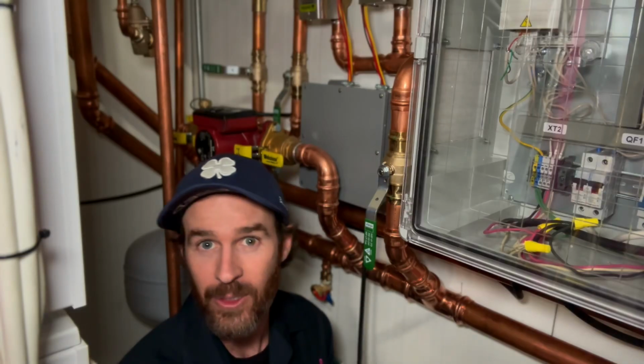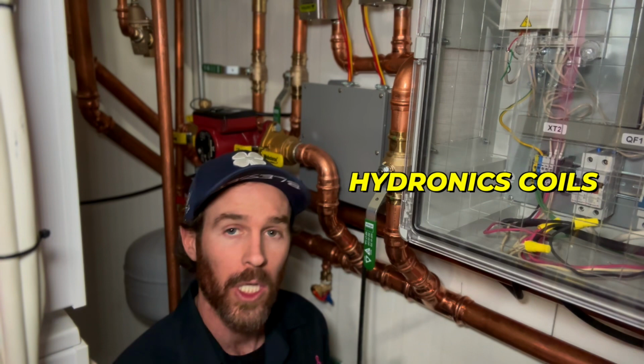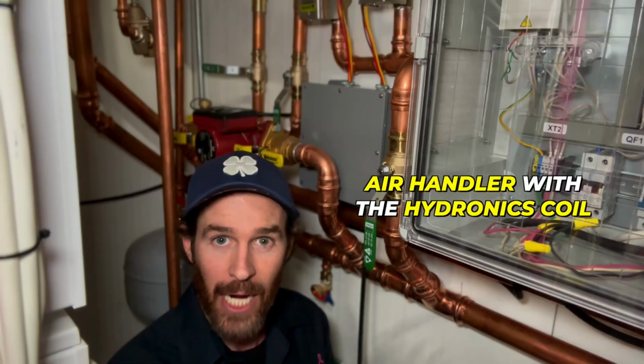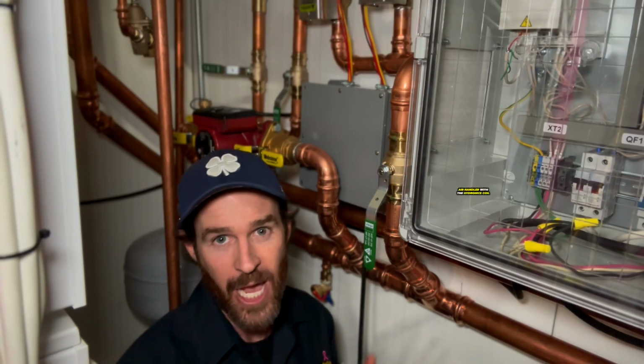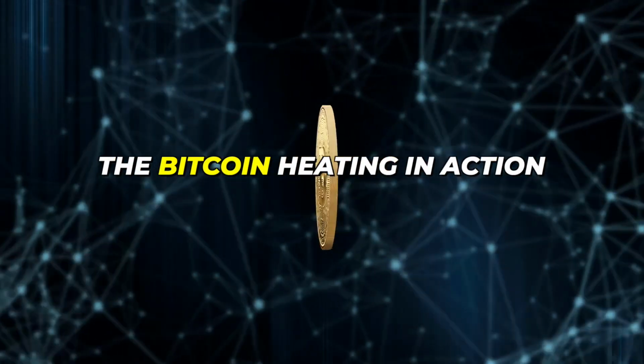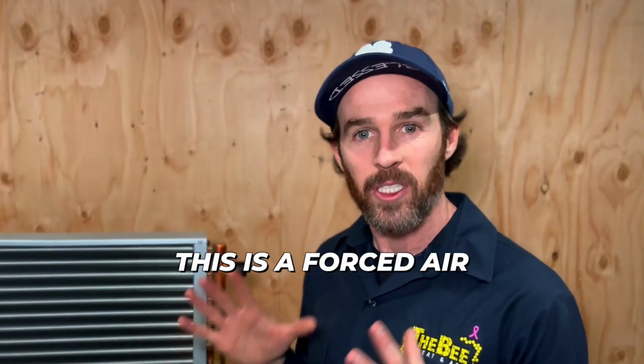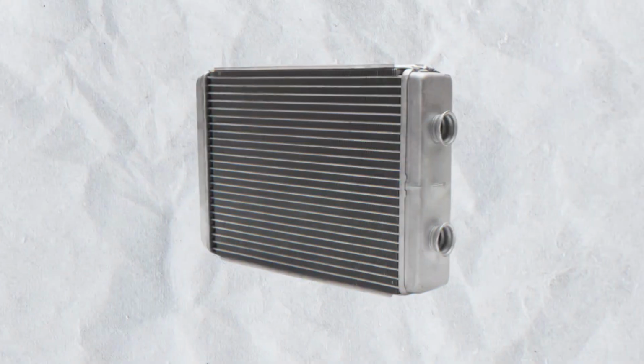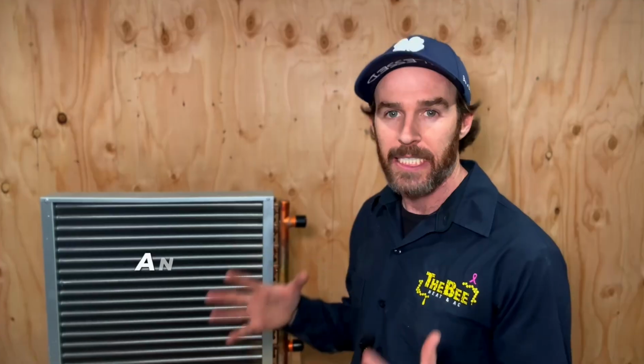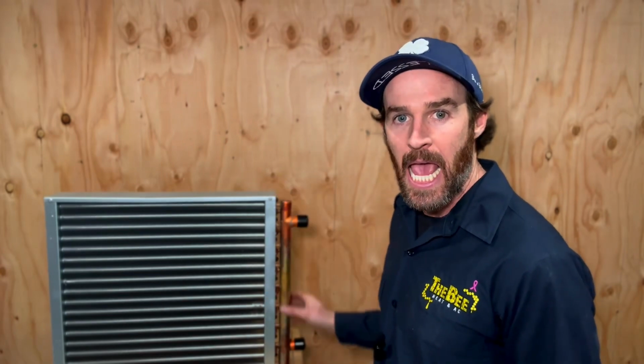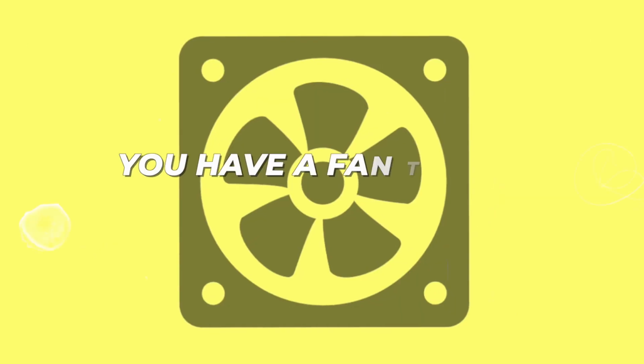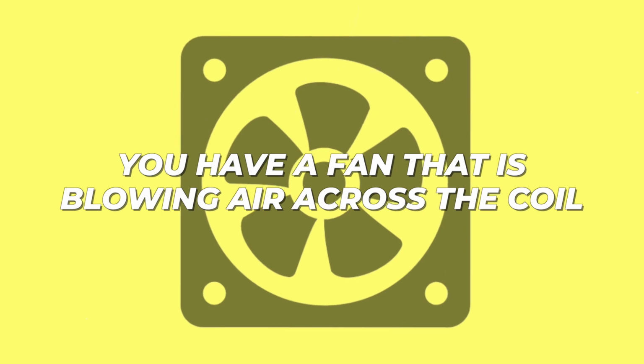Let's go take a look at one of these hydronics coils, and then lastly I'll show you the air handler with the hydronics coil so you can see the Bitcoin heating in action. This is a forced air hydronics coil, and it looks similar to a radiator on a car, serving the same purpose. In a nutshell, you have hot fluid coming in and colder fluid coming out, with a fan blowing air across the coil.